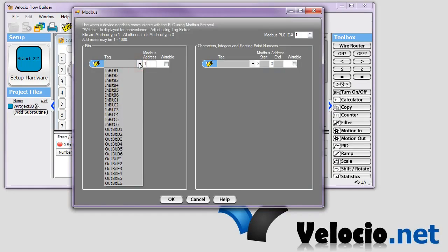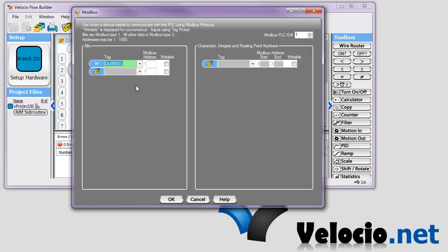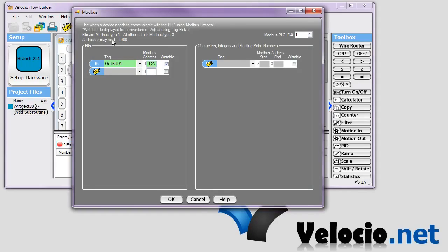So we will select the D1, the output D1 that we talked about. And when I hit Enter, you can see that it automatically assigns a Modbus address. You're not stuck with this address. You can use any address that's between 1 and 1,000 that isn't already assigned to another variable.